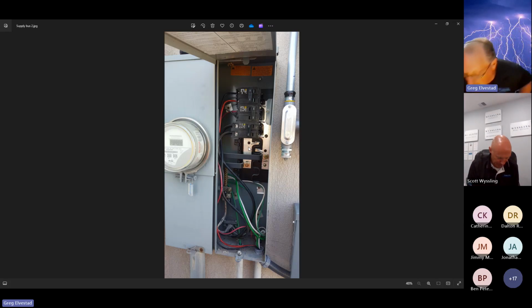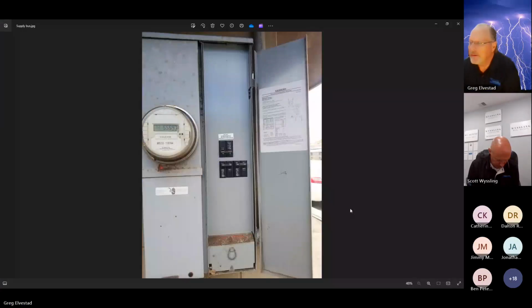Sometimes you'll have authorities having jurisdiction who don't understand this or have never seen this, and they tell you, well, that doesn't fit the 120% rule for bus loading. And you have to back them up and help them understand that, yeah, where do you turn this off? You can't. That's why it's supply side. Same thing as if this was just a sub panel with a main breaker and there were wires leaving here going to the panel, and you had a way to connect to that bus bar. So that's supply side. How do we connect on that panel? You use a breaker. Now, there's another example that I want to cover briefly that you may see, depending on where you are, is one like this.